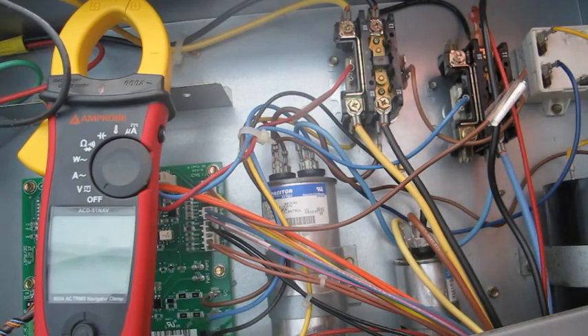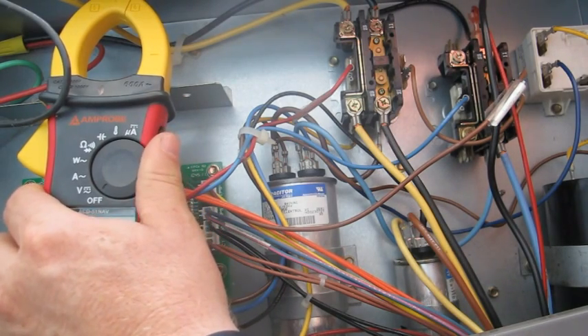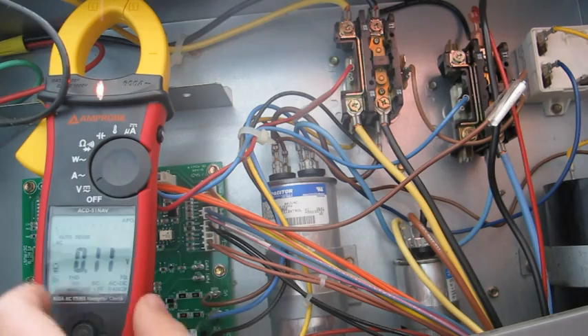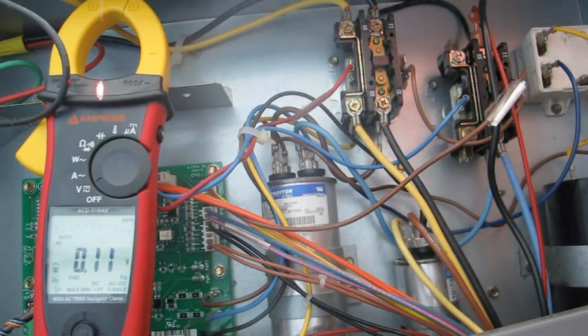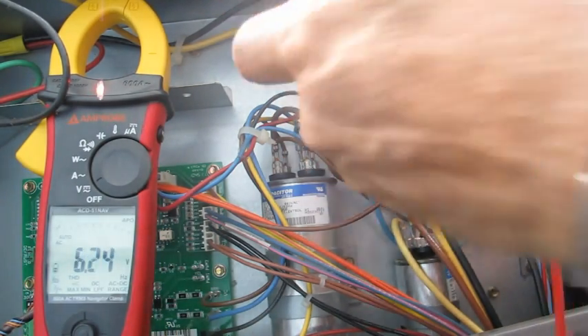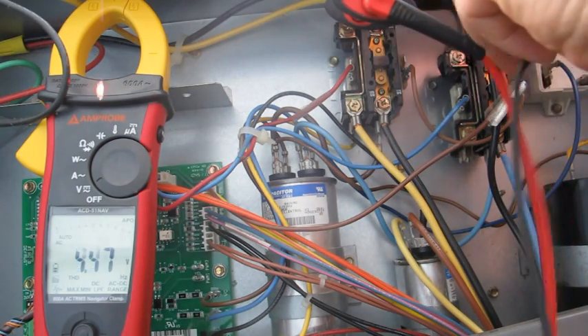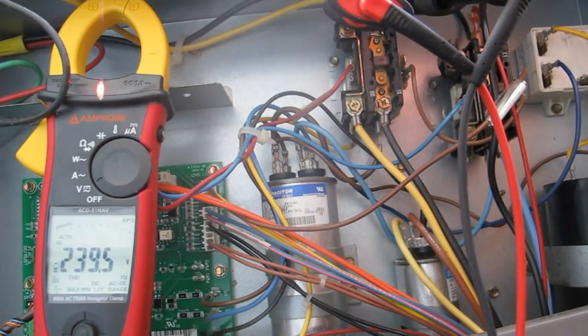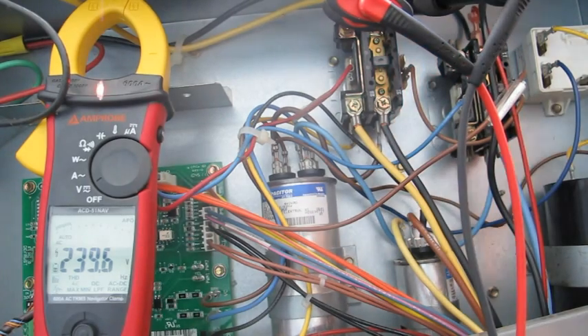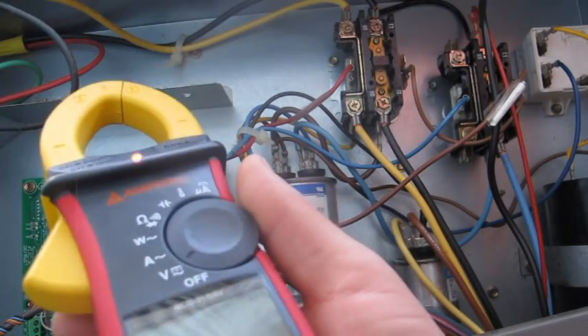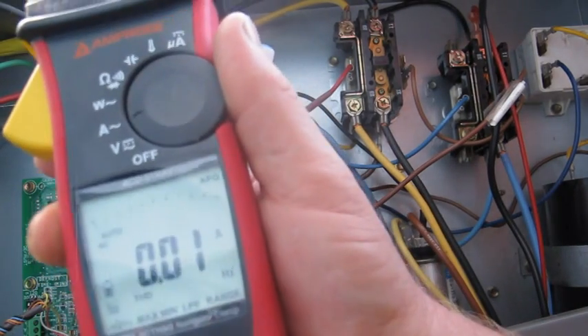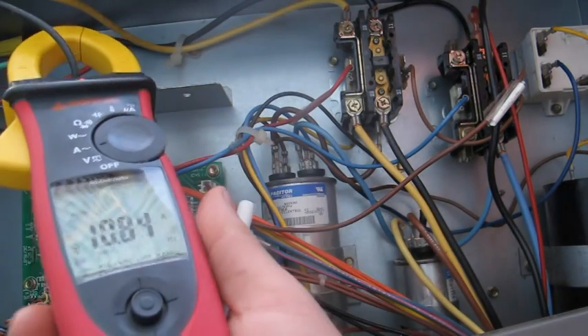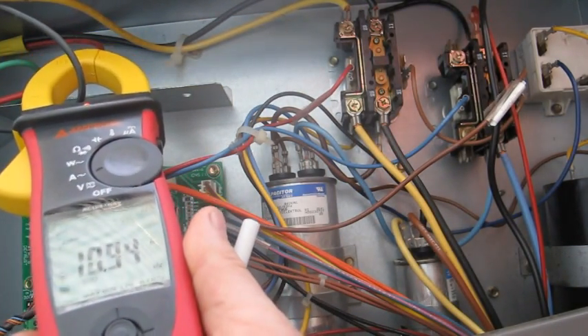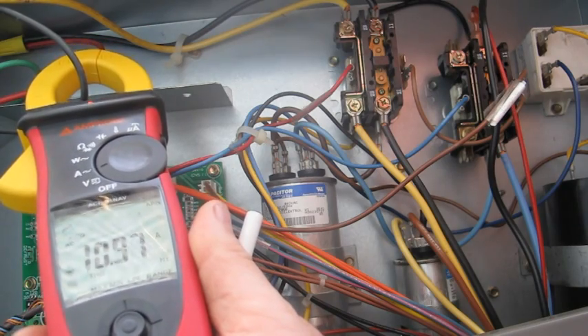If you didn't have this particular meter, you just set your volt meter to volts. Turn the light on, maybe it'll make it a little bit better. And you just measure your voltage. So right now I'm running at 239 volts. I'm going to record that. The next thing we're going to do is get an amp draw. Turn your meter to amps and clamp it around your wire. Right now we're pulling 10.9 amps.